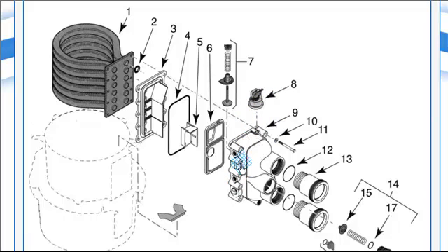It comes with new bolts. Line up the bolts and use lots of lubrication, because these threads sometimes are not nice. If it starts squeaking on you and you're not done being tightened in, back it out and lubricate those bolts more. I've seen it lots of times where people get frustrated. All I need to do is another eighth of an inch, and they start wrenching these bolts and they snap off. So be very careful putting these bolts in.